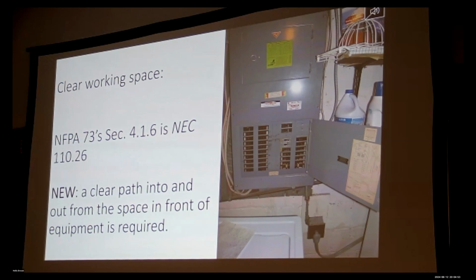But it is bloody dangerous to have an electrical panel where you don't have that, even if it isn't 30 inches by 3 feet and the full width of the panel clear, with a reasonable amount of working space. And I think that is a reasonable amount—certainly the idea that doors can open to 90 degrees and that the cover can be removed.